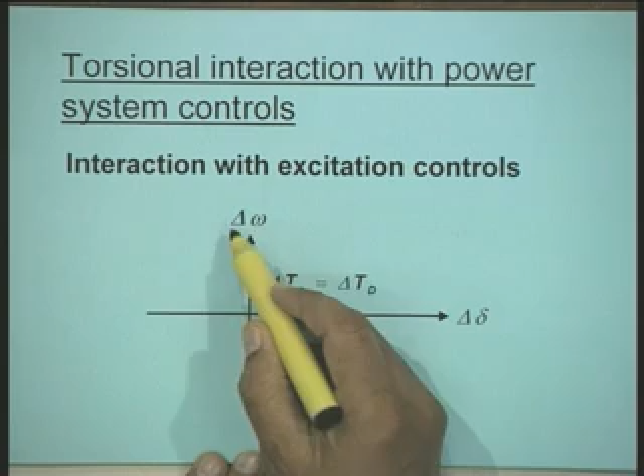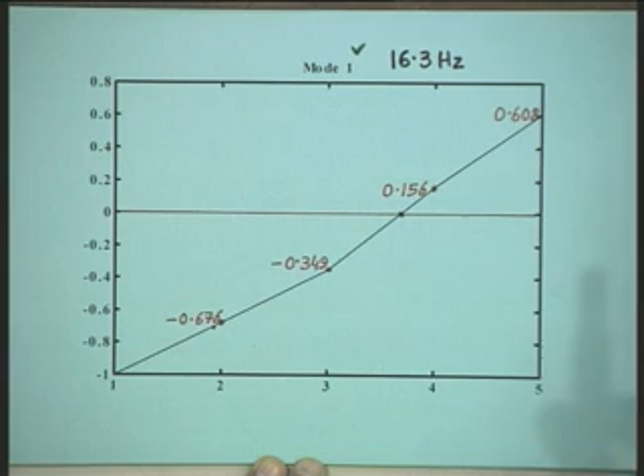the speed signal is sensed by using a speed transducer, and when we mount a speed transducer at a particular location, let us say at the generator end of the turbine generator shaft, then at that particular location the speed signal has a high component of the torsional oscillations. If you examine this diagram, for a typical turbine generator system, this is the mode shape corresponding to 16.3 hertz, and we can easily see that the component of speed deviation signal which is sensed at the generator end of the shaft is quite a large one, and this component when it is processed through the power system stabilizer will produce a component of air gap torque which will have a large phase shift between the speed deviation signal and the air gap torque produced.